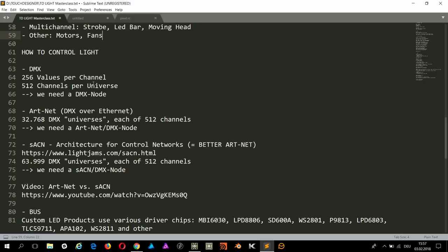Yeah, so to control light, there are different ways, different protocols. The oldest one, or the standard one, is DMX. And DMX is hardware based. That's what we saw on the cable before. You really cable all the devices. And on one chain, on one cable, you cannot put just one fixture. You can also put a lot of them behind. You go into one device at the input, and from the output to the next one, you build up your own chains. The only thing you have to keep in mind is that from the address space that you have, you can consume a maximum of 512 channels. That means if you have RGB lights, you have to divide it by 3. That's the maximum number of spots you could put into one chain.